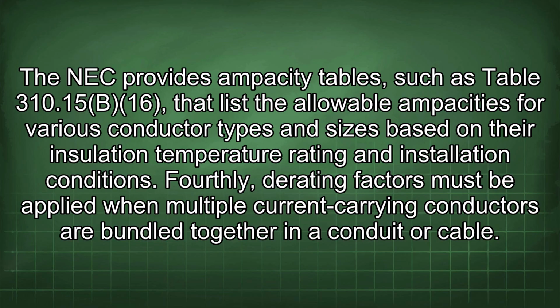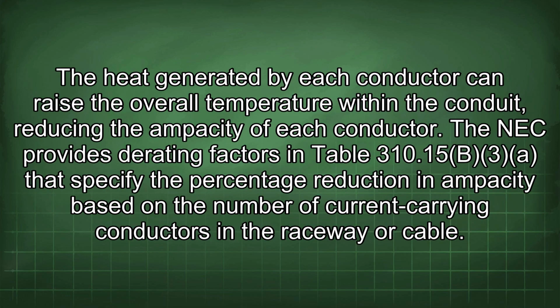The NEC provides ampacity tables, such as Table 310.15(B)(16), that list the allowable ampacities for various conductor types and sizes based on their insulation temperature rating and installation conditions. Fourthly, derating factors must be applied when multiple current-carrying conductors are bundled together in a conduit or cable. The heat generated by each conductor can raise the overall temperature within the conduit, reducing the ampacity of each conductor. The NEC provides derating factors in Table 310.15(B)(3) that specify the percentage reduction in ampacity based on the number of current-carrying conductors in the raceway or cable.